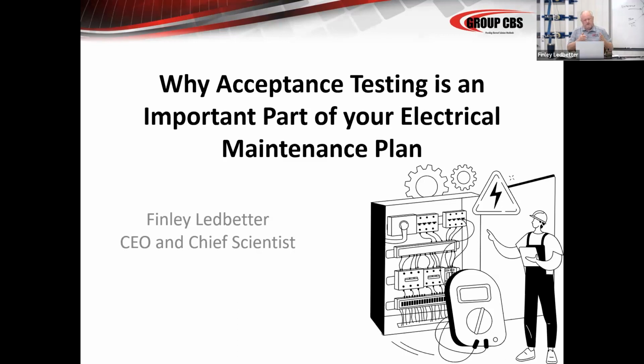So basically, if I test today, I test tomorrow, I test the next day. If I did a complete electrical test every day, I would feel pretty comfortable that my system was reliable. But you can't do that. So you can only test it one time, and then you wait for a period of time before you test it again. In that interval, you want this equipment to be reliable. That requires a lot more than testing. You cannot test in reliability unless you want to test it every minute, every day, every week, every month, which is not practical. So to make it reliable over this period of time, you have to have building blocks. The ATS or the acceptance testing is simply one building block in that overall plan to make your plant reliable or to make your electrical system reliable.